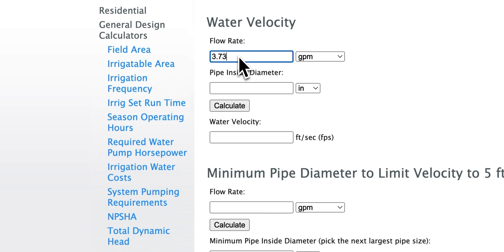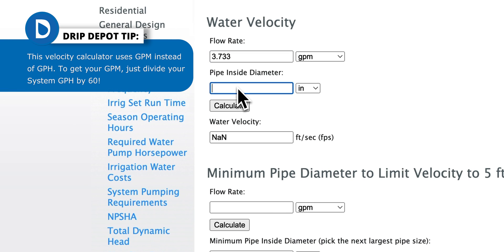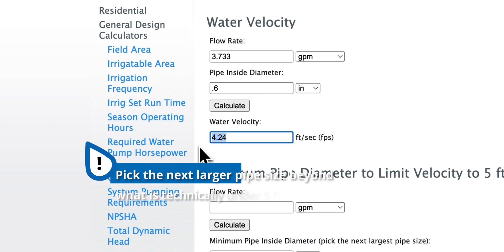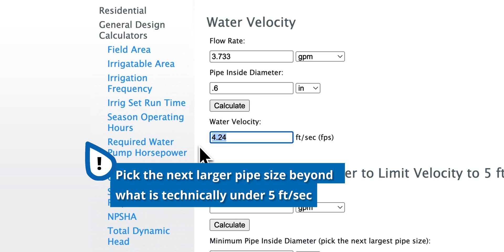224 gallons per hour, or 3.733 gallons per minute, going through one half inch tubing has a water velocity of 4.24 feet per second. That is within the parameters of the 5 feet per second rule. Between the answers you get for friction loss and velocity, you want to go with a mainline size that falls below 5 feet per second with as low friction loss as possible. A good rule of thumb is to pick the next largest pipe size beyond what is technically under 5 feet per second. It's always good to minimize friction loss, as friction causes wear on components, but it is a balance between that and the cost of a larger diameter mainline.